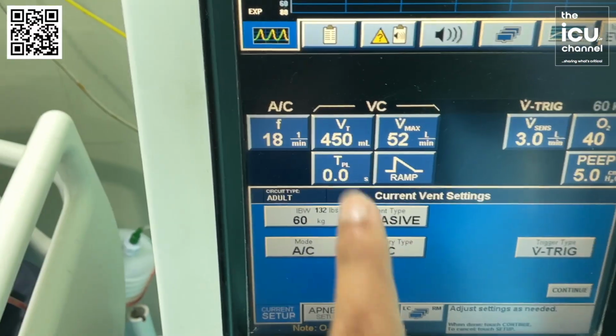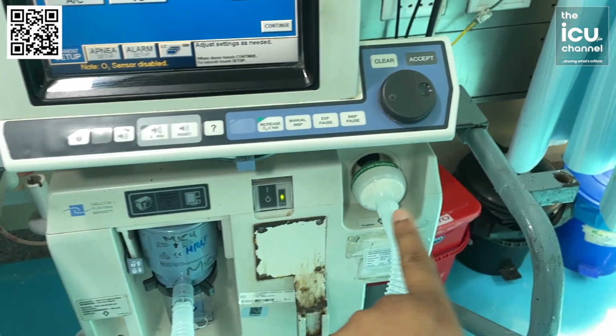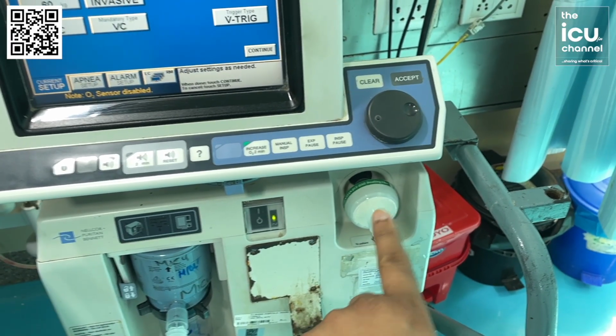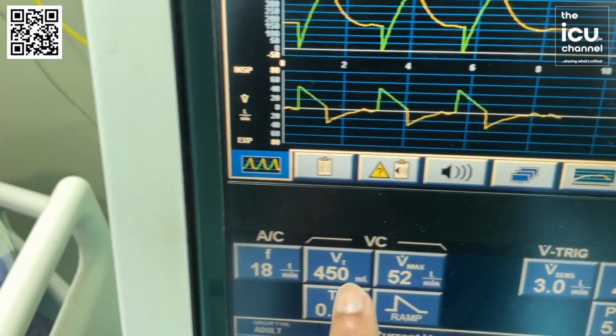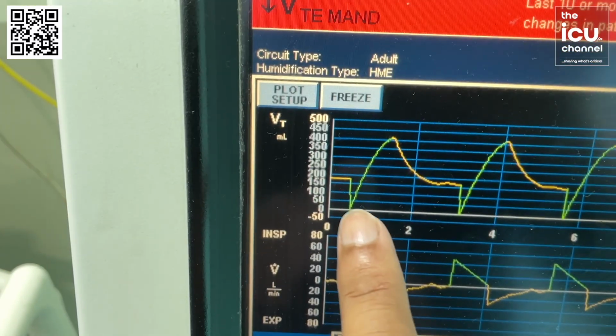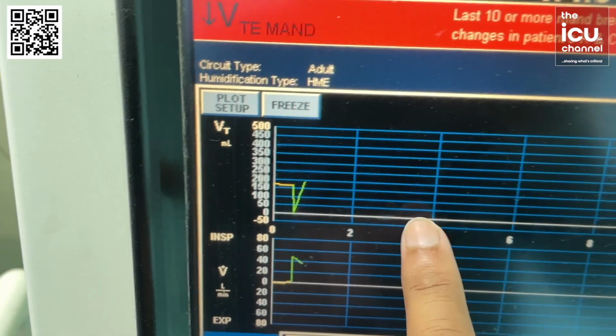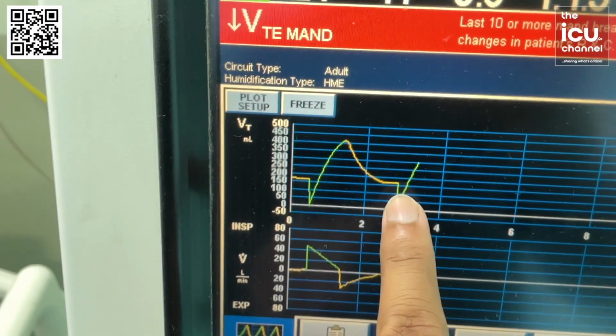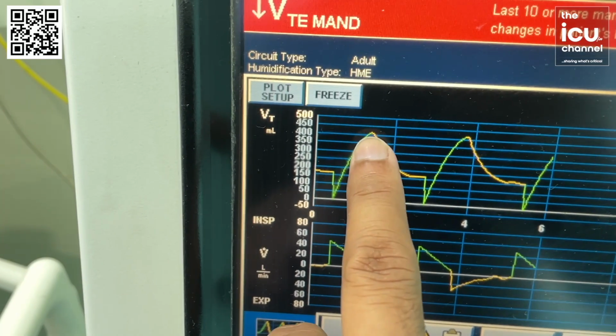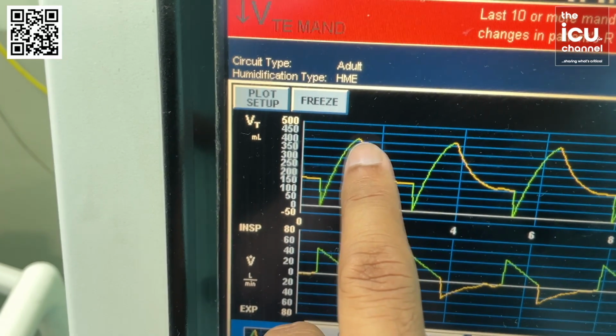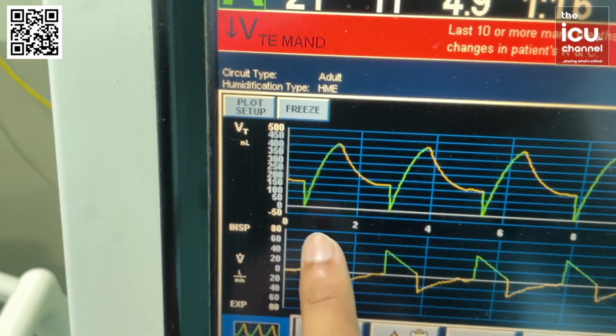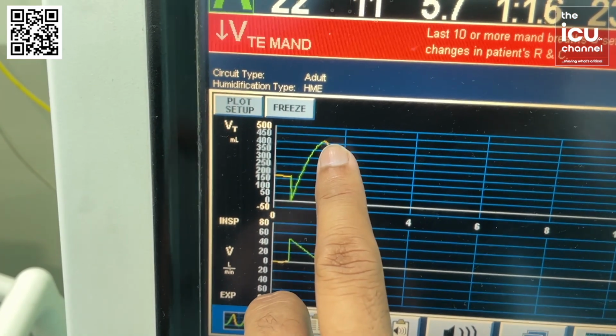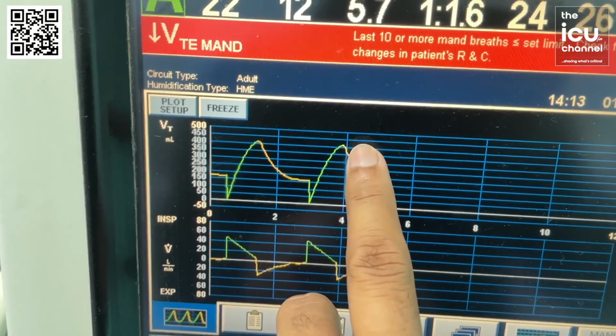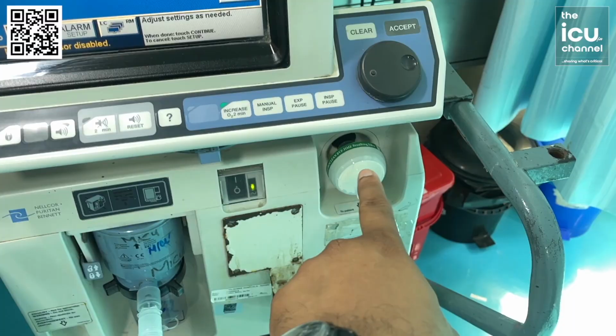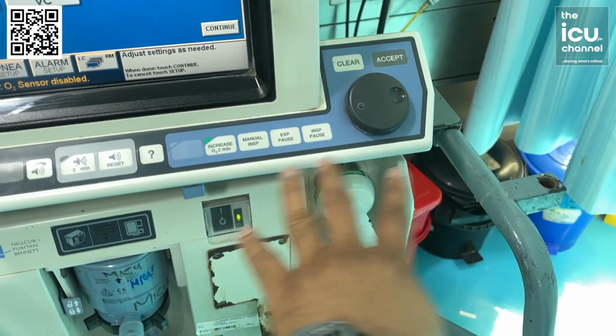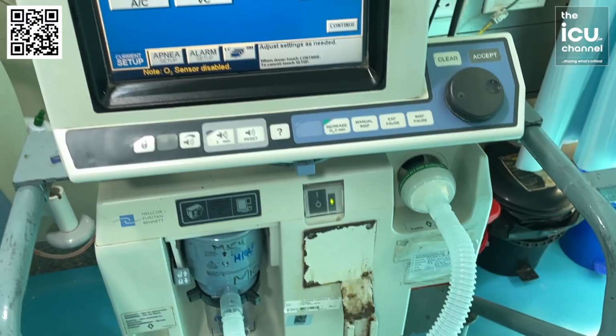So let's see whether this inspiratory limb is delivering 450 tidal volume or not. How will we check? We'll check on the graph. 450 was set. Now we'll see that. You see, this is the inspiratory limb and this is the expiratory limb. Here you can see it reaching around 450. The plus minus 2-3% is the leak which is expected. So it is delivering 450, 430, 440 like that. So that means this inspiratory limb is generating 450 tidal volume. The sensors are working fine, and it is going to the patient.